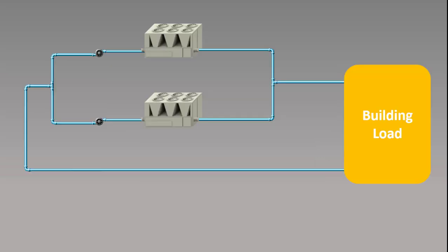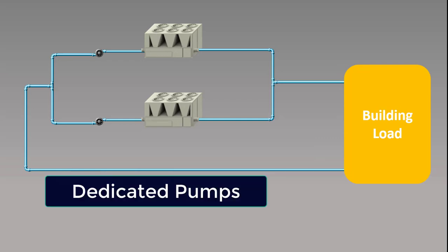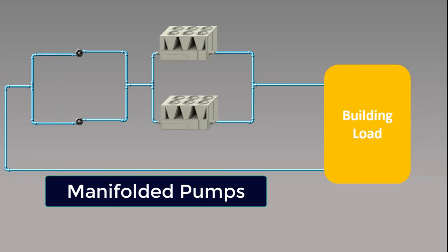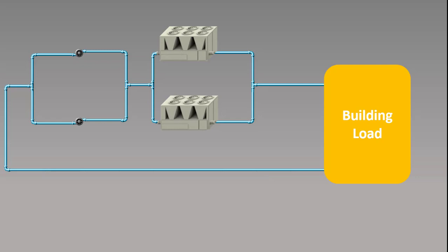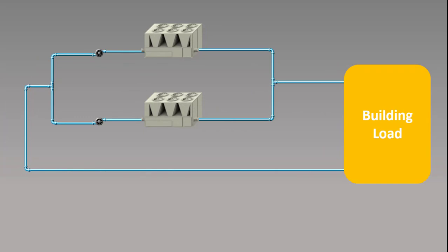A constant speed primary chilled water system is shown with dedicated pumps, where a pump is dedicated for each chiller. The other configuration can be manifolded or header type — both can be used based on design preference and each has its pros and cons. For our discussion, we will consider the dedicated primary chilled water system configuration. Now let's have a look at the different components of this system for its control and monitoring from the BMS.